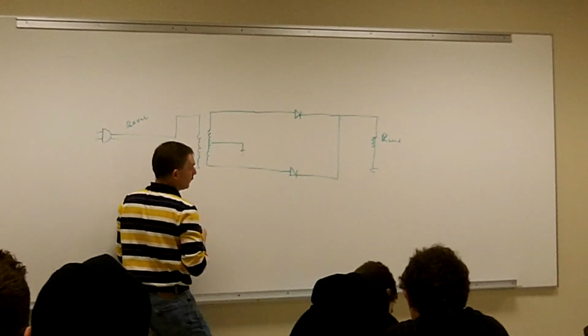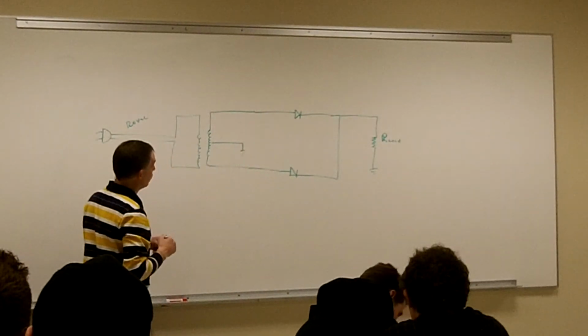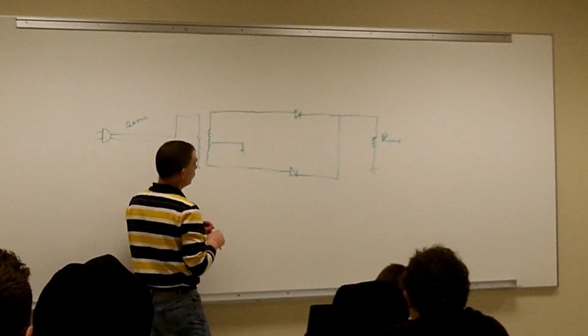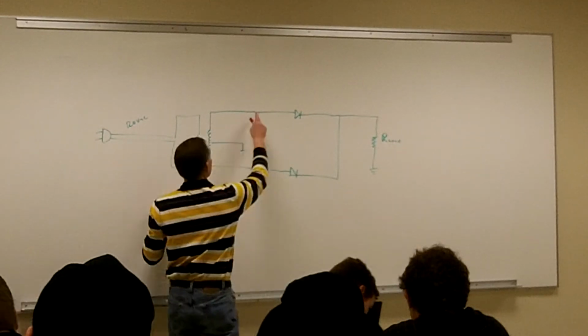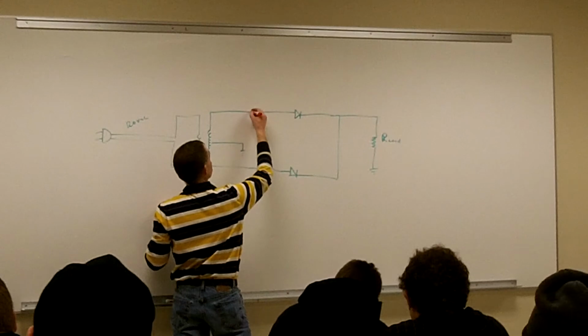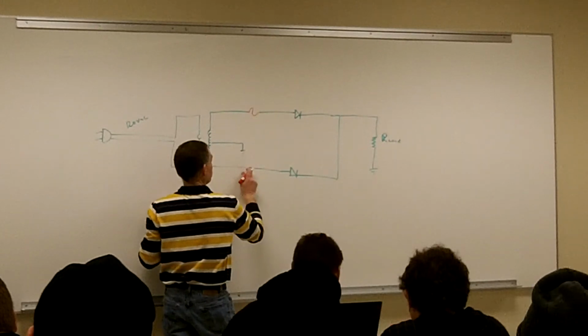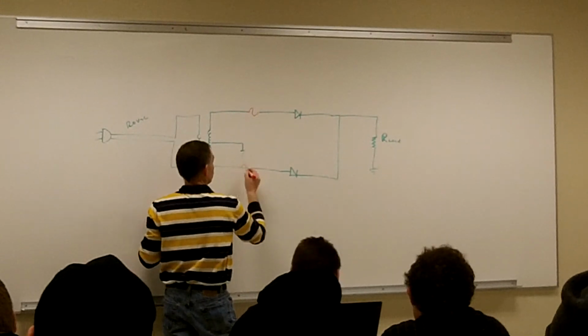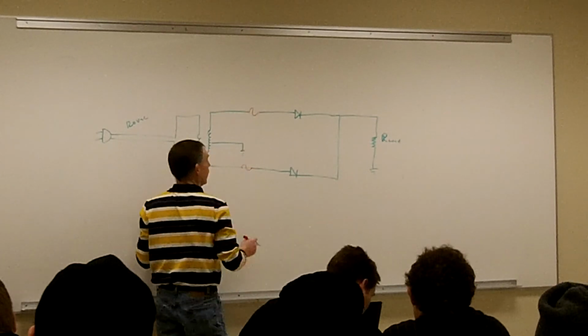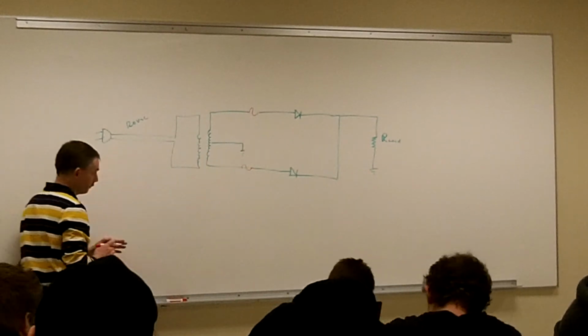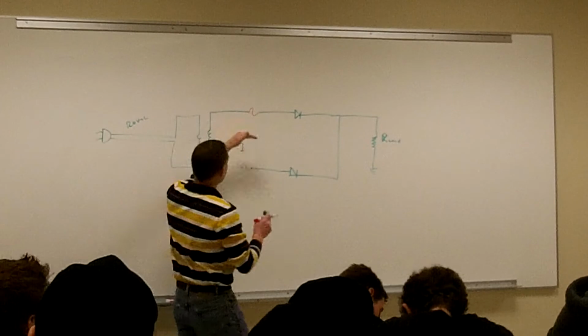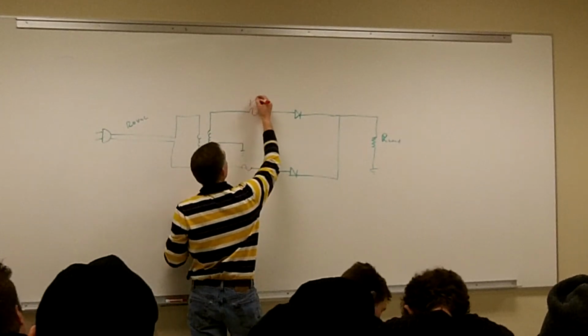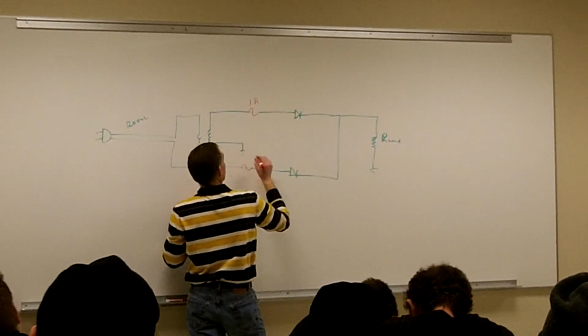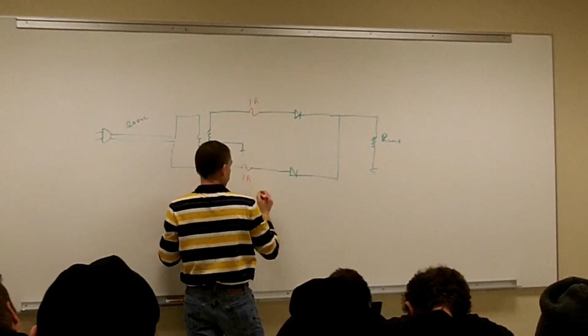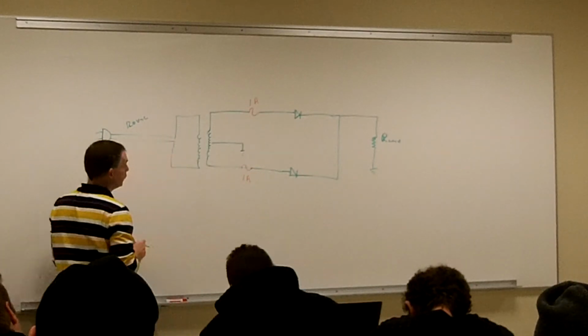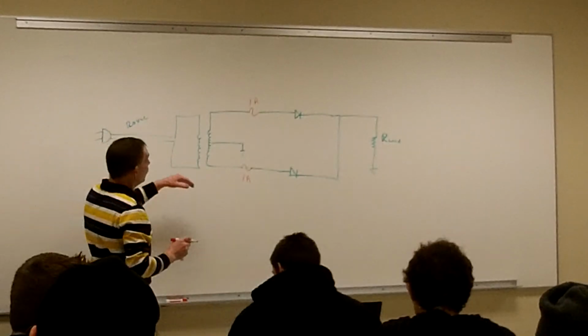So if you're going to protect a circuit using our center tap, what you'd have to do is protect your fuses on both legs — you'd have to use 2 fuses. Each one of these fuses would have to be rated at 1 amp, and that would protect your fuse and your transformer.